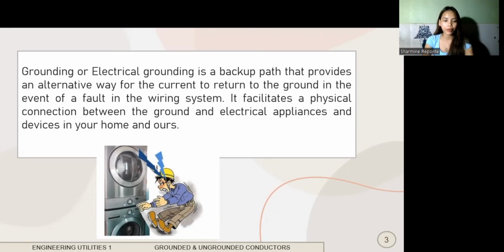So we have here an illustration. The washing machine here might have a fault in its system that causes overloading or short circuit. If that faulty current has nowhere to go and just stays in the washing machine, it might cause an electric shock to whoever touches the washing machine. Same in this picture, the man touched the washing machine, which caused him to be electrically shocked. But if there is grounding in a situation like this, the faulty current will flow back to the ground without causing any problem.